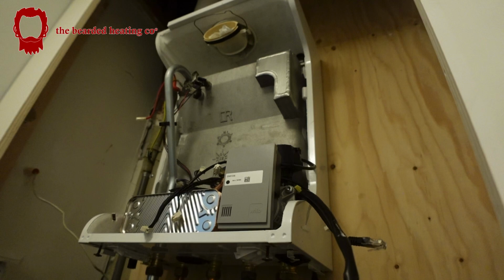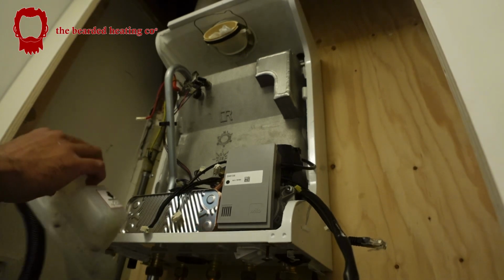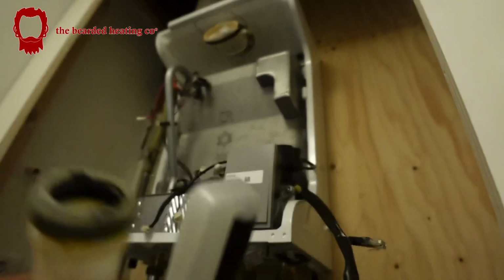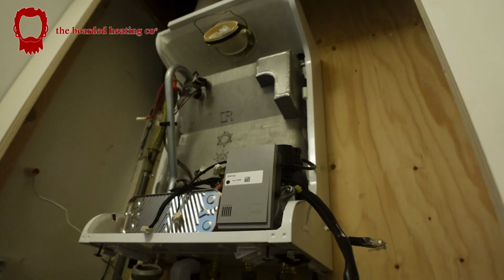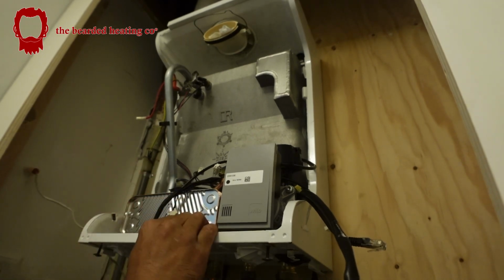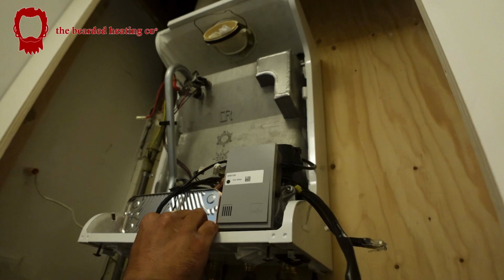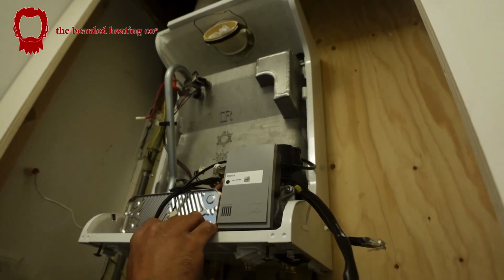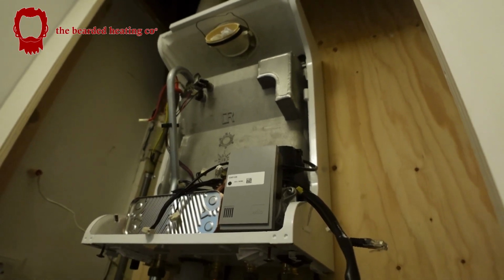Perfect. Now let's put the bottle trap back in, because I want to flush the heat exchanger out. So put that back to the drains. The bottle trap also, as part of the package, there's a new seal for the bottle trap, which I will put on after I flush the heat exchanger out.